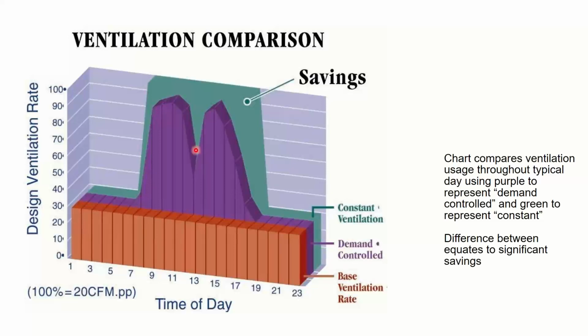Now at the school, you're not going to see a dip for lunch for the whole school, but you're not going to be putting these sensors in for the whole school. You're going to be putting them in for each room. So in every room, I'm going to see at least one dip, if not multiple dips, depending on where the kids are moving around the building. So this is an office building with a 2-hump profile. A classroom might have 4 or 5 humps because kids leave to go to recess. They come back. They leave to go to PE or whatever it is. So it'll be a little bit different.